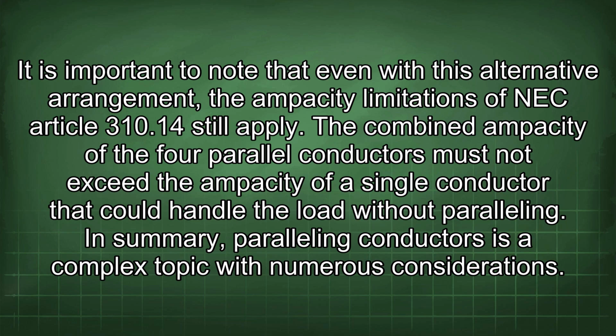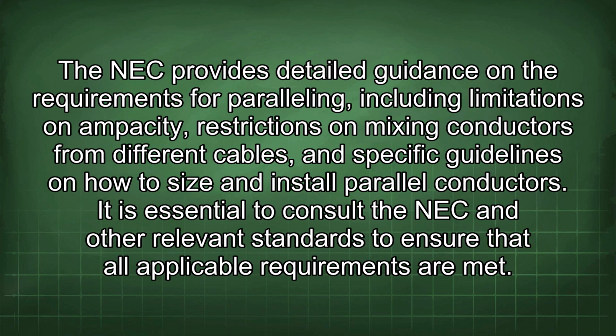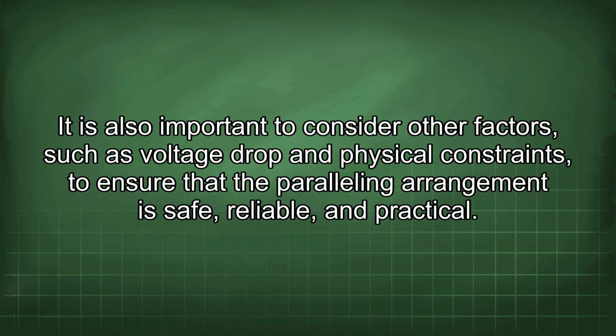the load without paralleling. In summary, paralleling conductors is a complex topic with numerous considerations. The NEC provides detailed guidance on the requirements for paralleling, including limitations on ampacity, restrictions on mixing conductors from different cables, and specific guidelines on how to size and install parallel conductors. It is essential to consult the NEC and other relevant standards to ensure that all applicable requirements are met. It is also important to consider other factors, such as voltage drop and physical constraints, to ensure that the paralleling arrangement is safe, reliable, and practical.